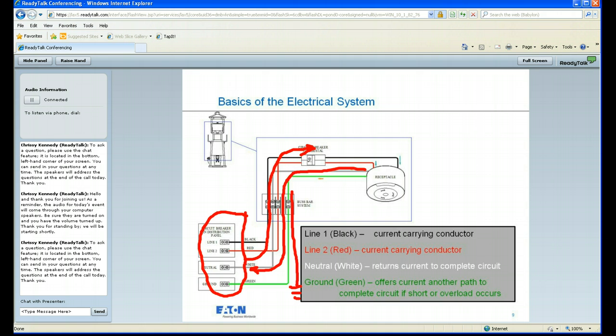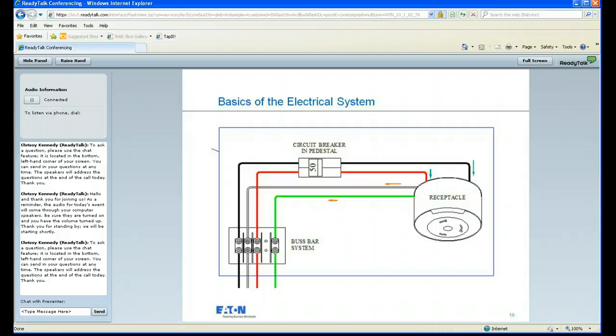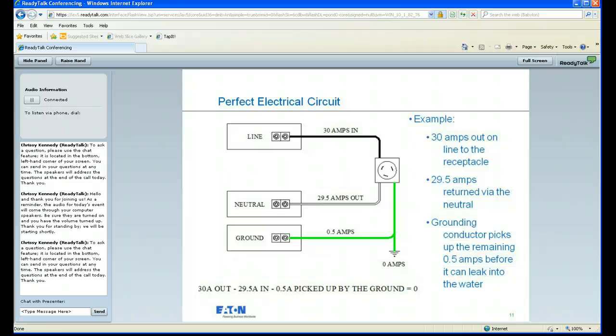And this green line here on the bottom is what is catching any current that is not completed through that neutral package. So anything going out, it's kind of a simple way to look at it, but what goes out should come back, and what doesn't come back should be picked up by the green wire or the grounding wire if everything is working properly. Again, I don't know how well you can see that cycle through what we just looked at, but this is just a zoomed-in picture of what you were looking at, where the black and red wires are sending the electricity through the receptacle, and the returns are going back on the white neutral and the green ground.